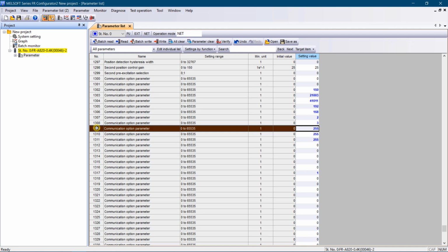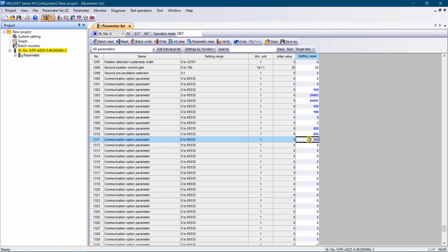The next parameters are 1309 to 1312. Those are to set the subnet mask. Mine is 255.255.255.0. By setting your IP address, make sure that your VFD will be in the same LAN as your PLC.